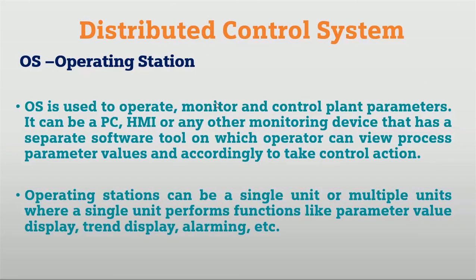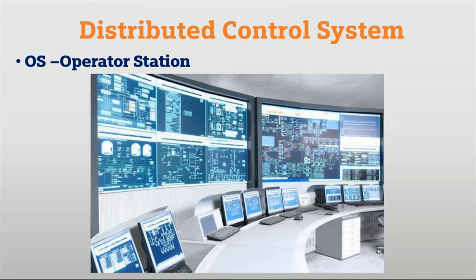The second important element is the operating station. The operating station is used to operate and monitor the control plant parameters. It can be a PC, HMI, or any other monitoring device with a separate software tool that operates and views process parameters and takes control actions. An OS station can be a single unit or multiple units that perform functions like parameter display, trend display, alarm management, and process control with real-time applications. Different stations can be placed and from the stations we can monitor in real-time, with graphical representation for the process, trend alarms, and process parameters.